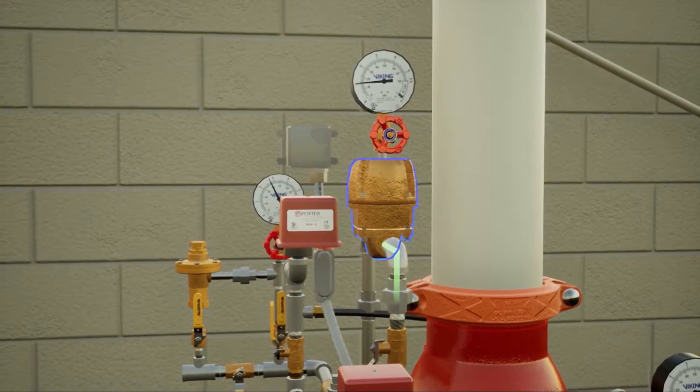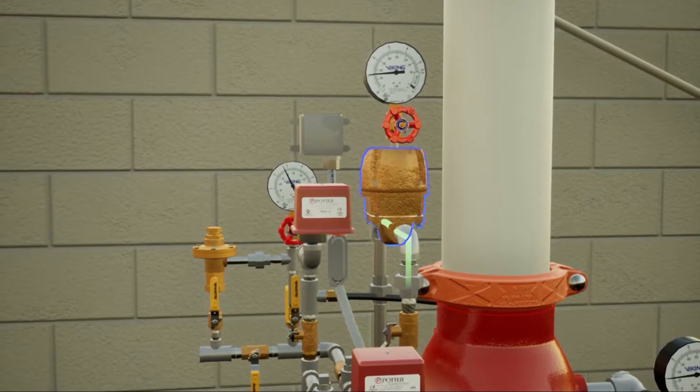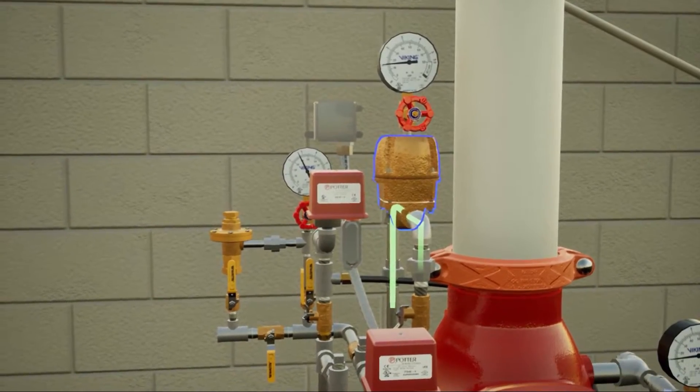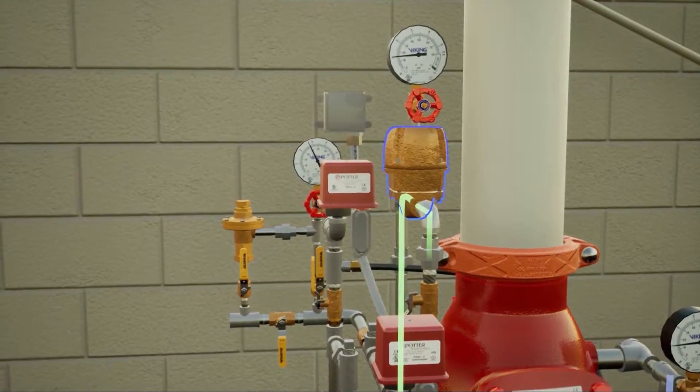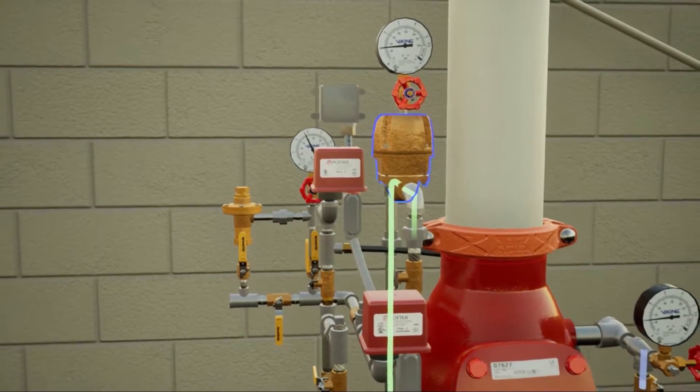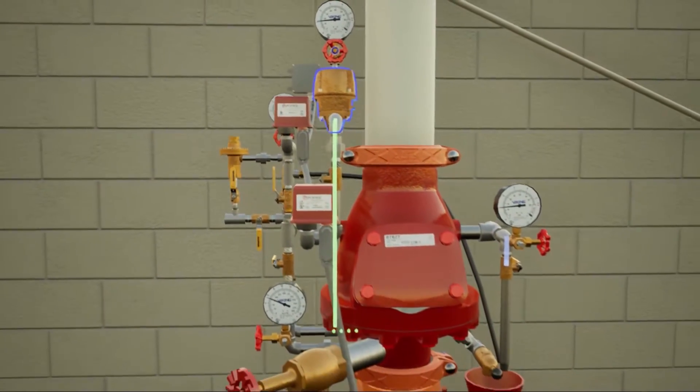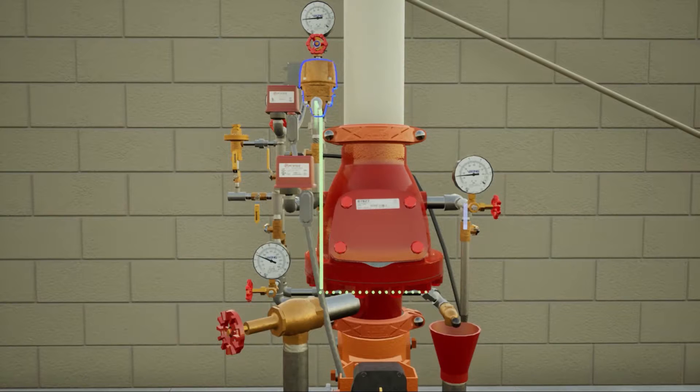If the system is equipped with an accelerator, a sudden drop of air pressure will cause the accelerator to activate, directing air pressure from the system side or outlet side of the dry pipe valve to the intermediate chamber of the dry pipe valve.